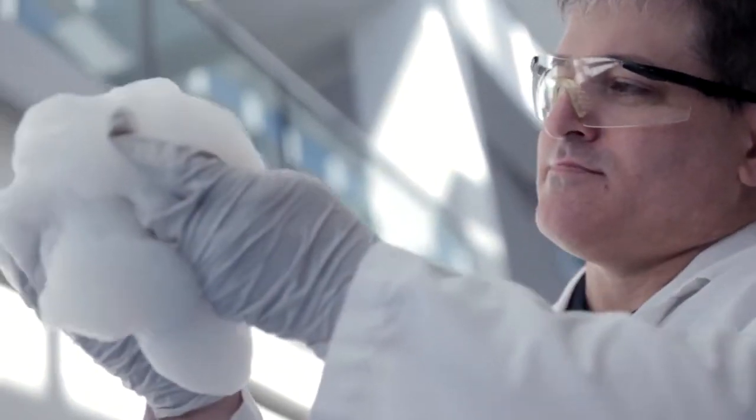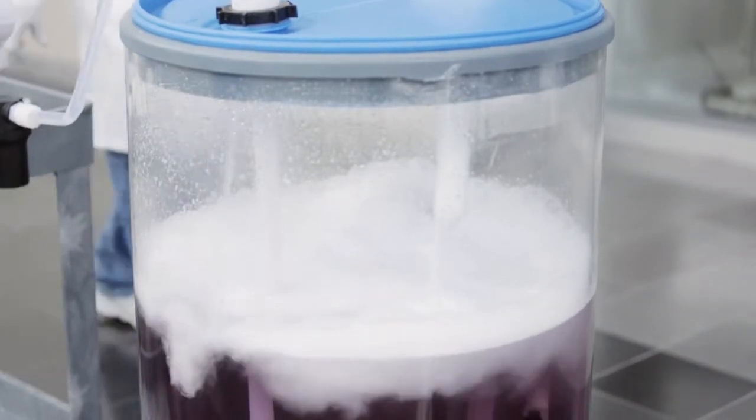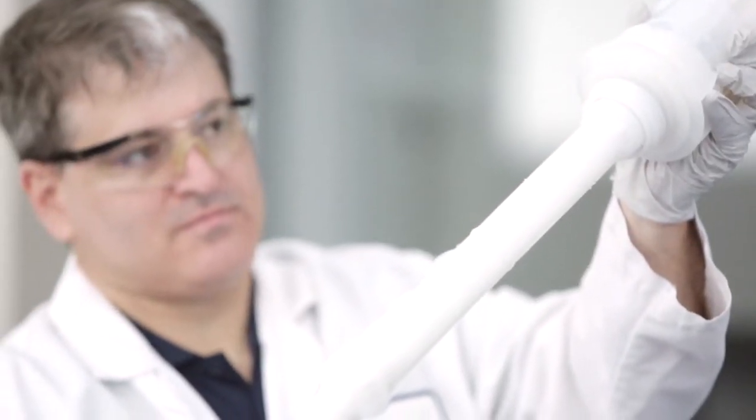The second reason that foaming is a big concern is the fact that the foam has a very large surface area and is prone to drying, especially in the dry conditions inside a fab. If the foam is allowed to dry out, it can entrain particles, it can entrain organics, polymers, and make a real mess. Basically, it can adhere to your dip tubes, your dispense heads, and those particles, once they start to build up, can flake off and get carried into the system and cause polishing defects.